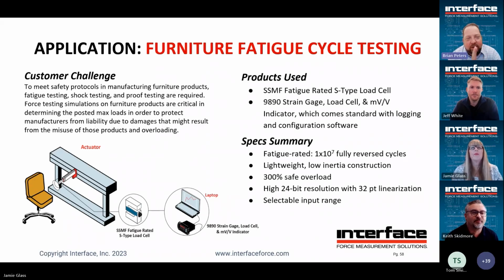Yeah, and two things on that. First, every time we calibrate a load cell, we're going to cycle it above capacity anyways. So that's part of our standard process. We'll put it in the rig. We'll run it usually at 120, 130% of capacity a few times. Then we start a cal. So every load cell that we ship has already been over capacity.